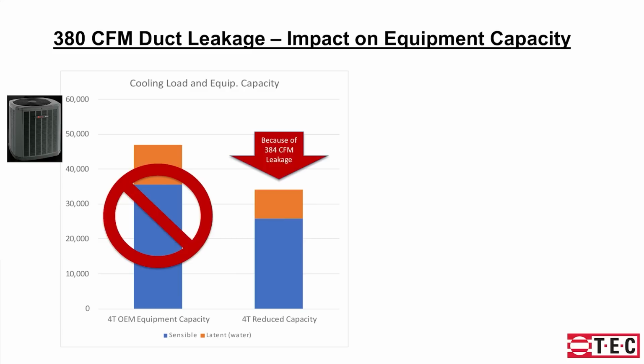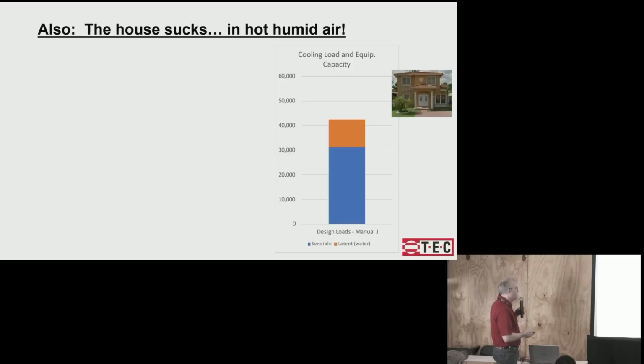Okay, so we don't have a 4-ton system anymore. We have a system that's much closer to a 3-ton system because of the air that we lost. Okay, so now let's look at what's happening on the house. Not only did we lose a bunch of capacity, the house sucks. It sucks hot air in. That's what happens when it's depressurized.